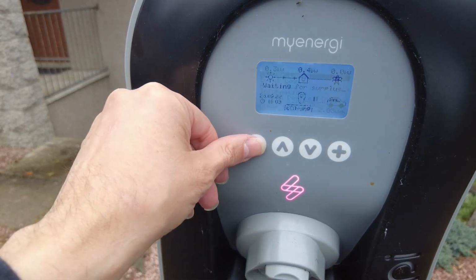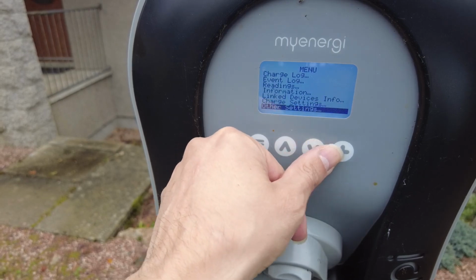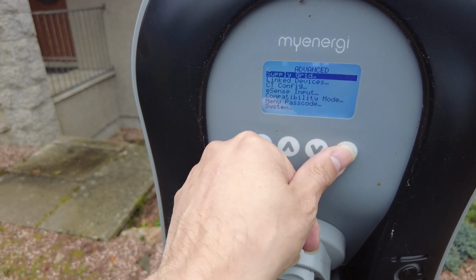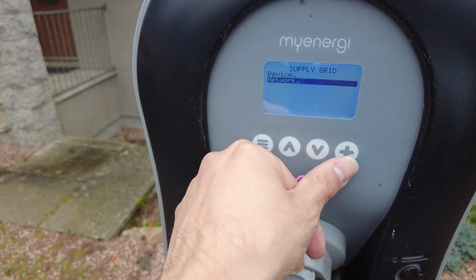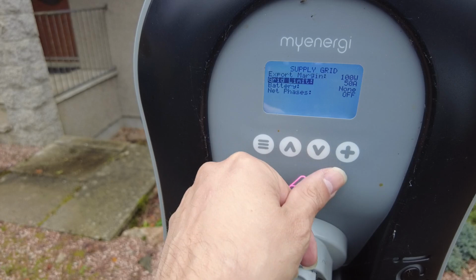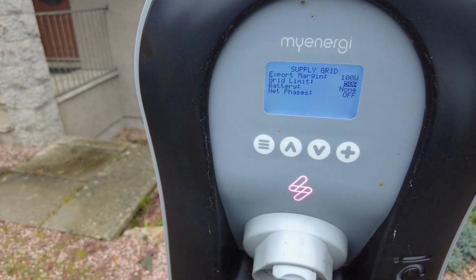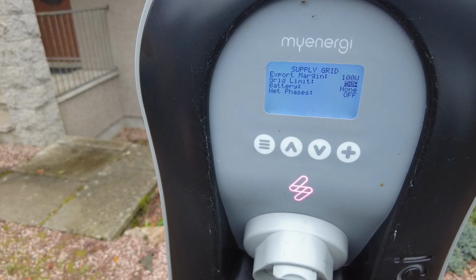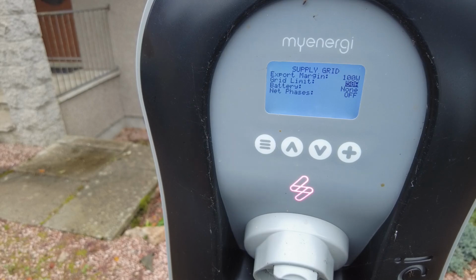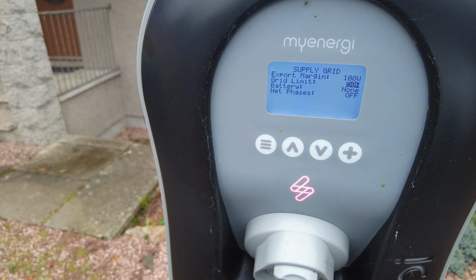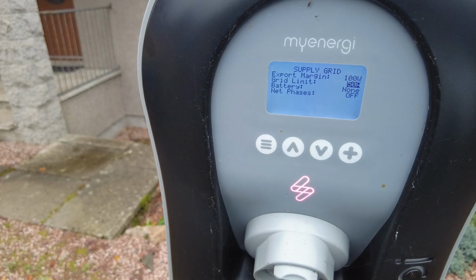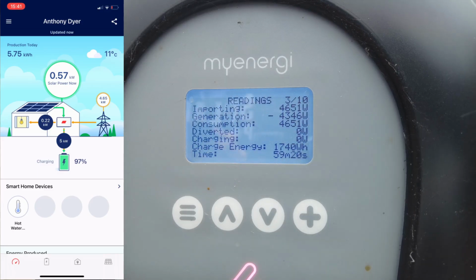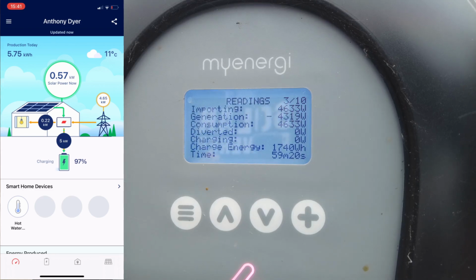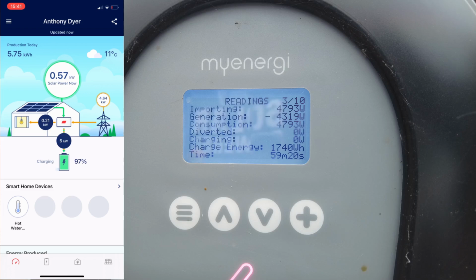So if we go into menu and we go to other settings, we go to advanced, we go to supply grid, we go to network, you can see there's a grid limit, 50 amps. So this will limit the current coming into the house when you've got other loads in that house, and it will limit the current going to the charger. We don't want to upgrade the supply cable, that's far too expensive, and we don't want to do without this rather handy charger either. So what you can see is that we're charging the vehicle at 5 kilowatts and we are importing about 4.5 kilowatts.